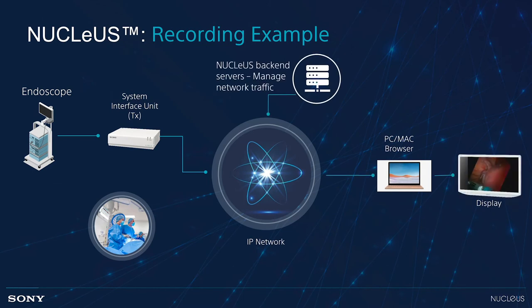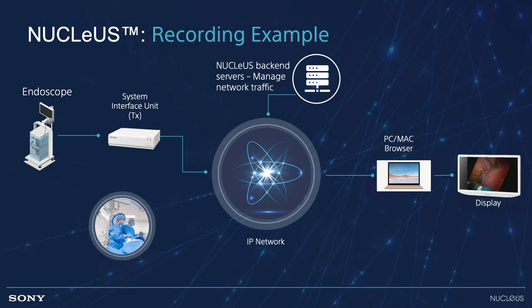For an ASC or a one-source room configuration like the one shown here, this is all that is needed. You have the one source — whether it's an endoscope, ultrasound, or whatever it is — then one encoder. That's all that's needed in the room to record. With the interface in place, stills and video in HD, 3D, or 4K are processed into the system. A very short list of equipment per room is what makes Nucleus, and in particular this application, so cost-effective.